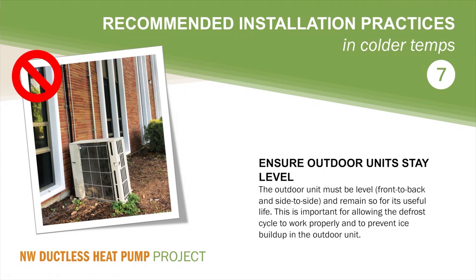The outdoor units must be level both front to back and side to side and remain so for its useful life. This is important for allowing the defrost cycle to work properly and prevent ice buildup in the outdoor unit.